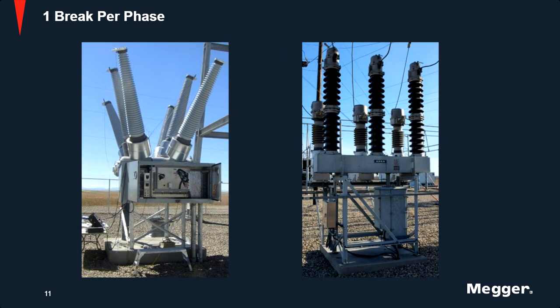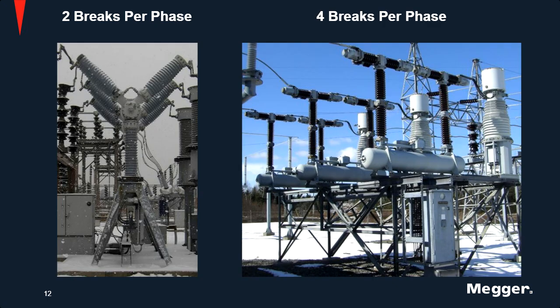Got a few examples here. So this is 1 break per phase dead tank and 1 break per phase live tank. This is an example of 2. I'm not sure if y'all can see my mouse or not, but you have 1 break here and then another break here. That's on a live tank. And this is the dead tank. If you look right here, you'll see a linkage between these 2 towers. So you have your 1 break there, 2nd, 3rd, and 4th.